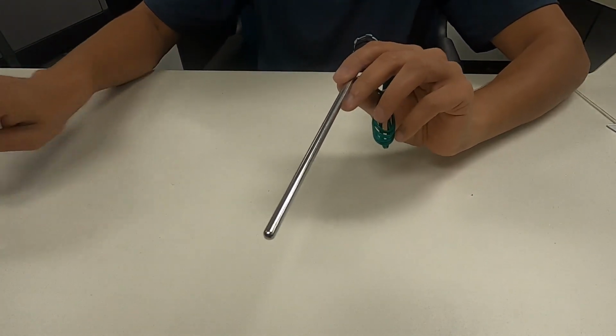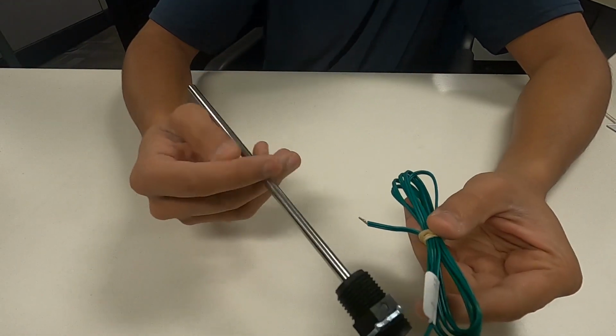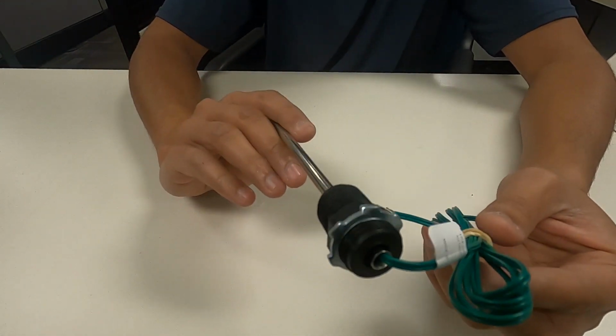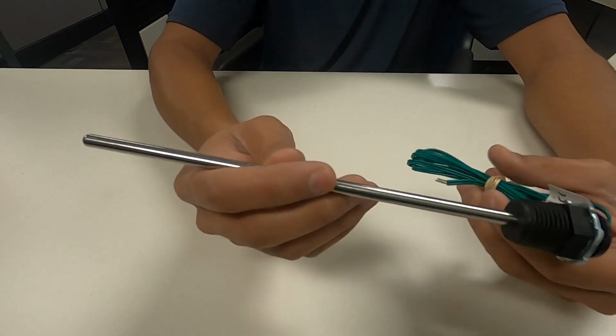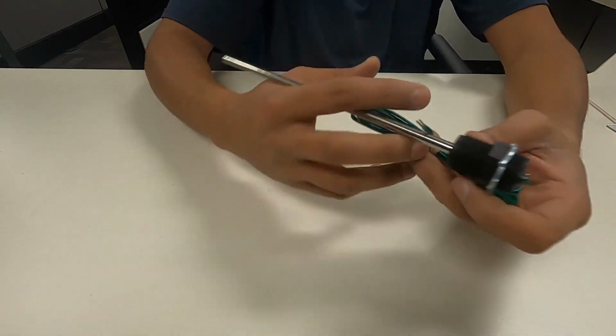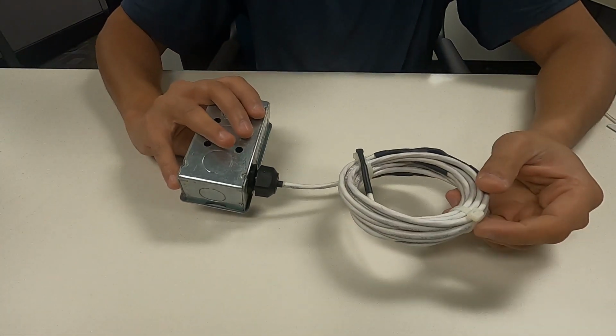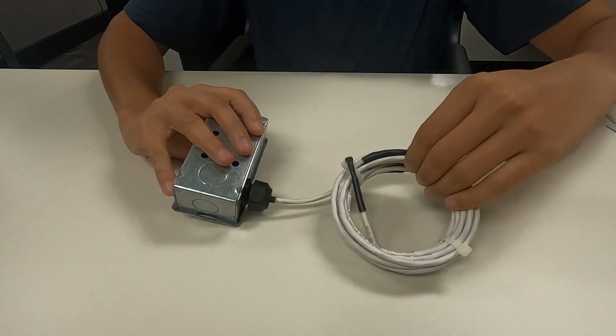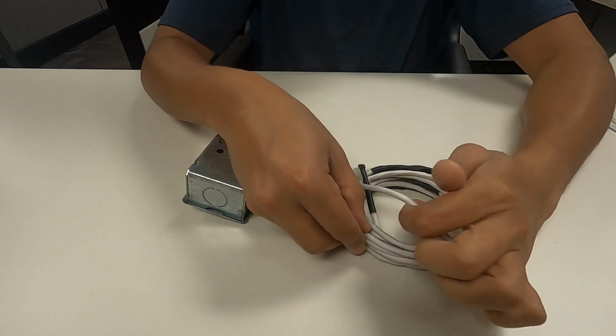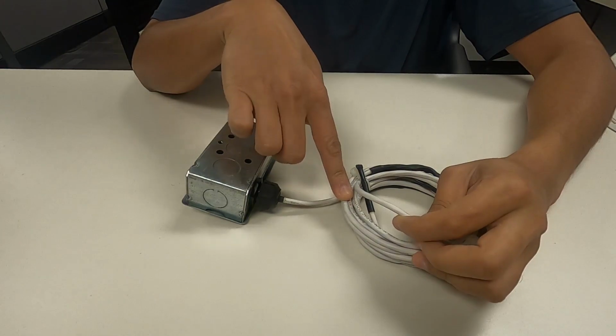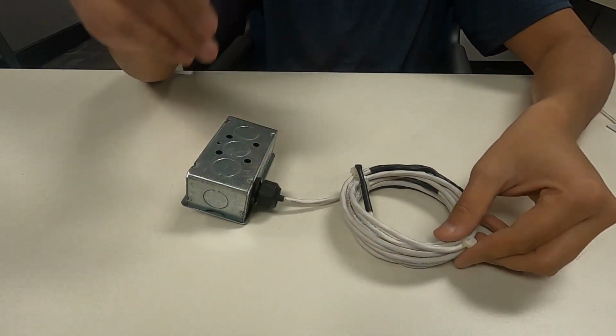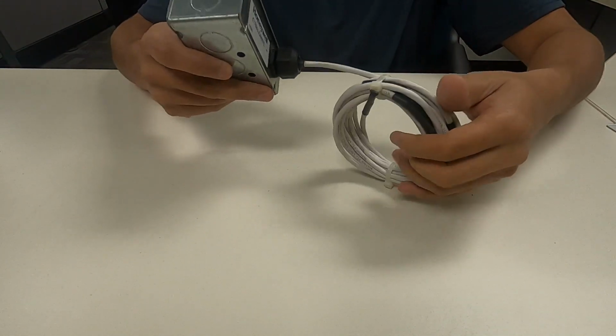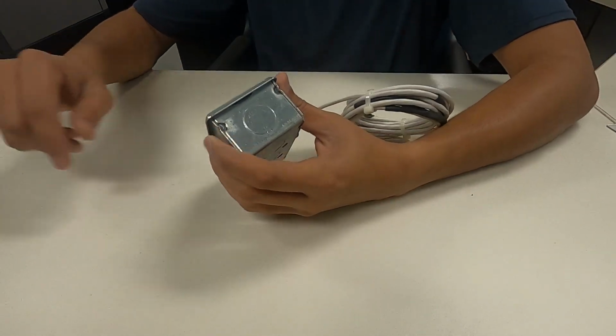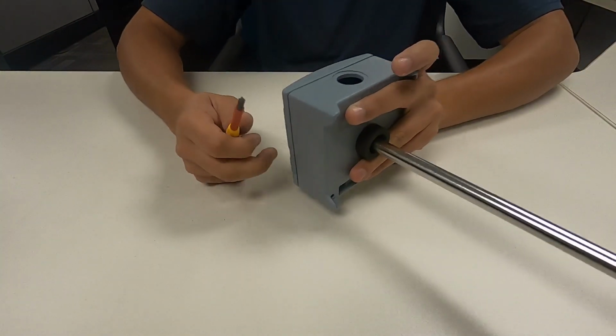Now, the selection process for the humidity sensors. In most cases, if you are using it for a commercial purpose, you might not have to go through a whole lot of specs or how it is built. All they care about is if the humidity is within their range. So it doesn't really have to boil down to what its accuracy is, or what the specs call for.